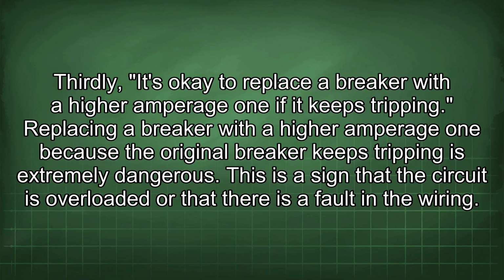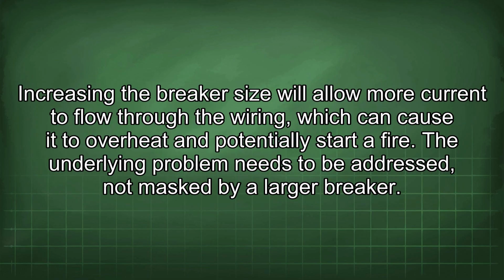Thirdly, it's okay to replace a breaker with a higher amperage one if it keeps tripping. Replacing a breaker with a higher amperage one because the original breaker keeps tripping is extremely dangerous. This is a sign that the circuit is overloaded or that there is a fault in the wiring. Increasing the breaker size will allow more current to flow through the wiring, which can cause it to overheat and potentially start a fire. The underlying problem needs to be addressed, not masked by a larger breaker.